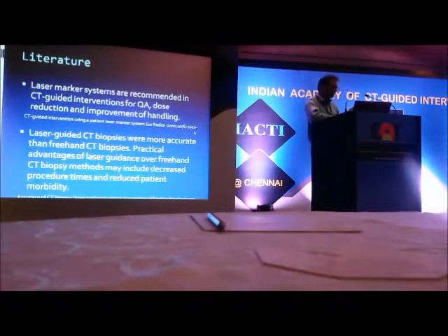So there is a lot of literature on laser assistance. The earliest ones I think came in the early 90s, but the first of the early commercial systems that came in was the SimpliCT. SimpliCT is not the only commercial laser guide that's available. There are other vendors also in the market. There are some vendors which have a freely movable unit like SimpliCT, where you can actually move the unit in and out. And there are also laser guides that are integrated with the CT table or can be attached permanently to the CT table. The advantage with the latter is that you do not have to align the unit each time because it is a fixed part of the CT table.